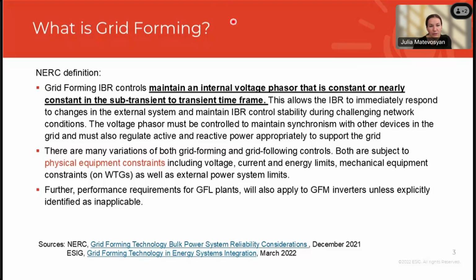So basically what it means is, if there are changes in external voltage magnitude, then there will be a nearly instantaneous response in reactive current coming from the grid forming inverter-based resource. If there are changes in voltage phase angle, there will be an instantaneous reaction in terms of active current provision from the grid forming inverter-based resource. So those are the two expectations, and you'll see them in the specifications as well.